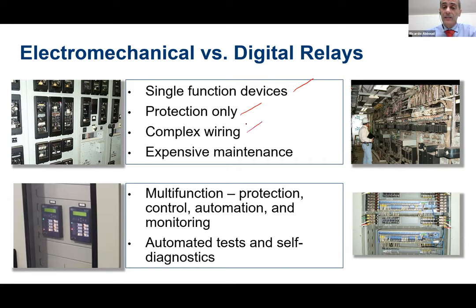Okay? Usually what you have is a complex wiring related to electromechanical technology. So you need to perform all of that parallel and series association of output contacts using wiring, and this translates into a very complex design and a lot of room or a lot of space necessary to accommodate all of those relays and all of that wiring. And also to keep the performance of the electromechanical relays, you need to perform an expensive maintenance. So it's really hard to keep the relays working properly. So you need to have a very good and very expensive maintenance.